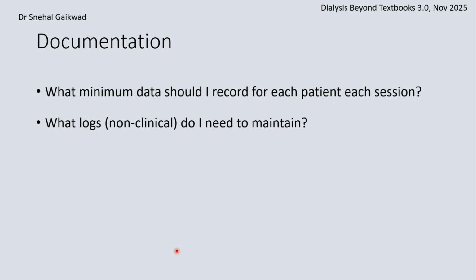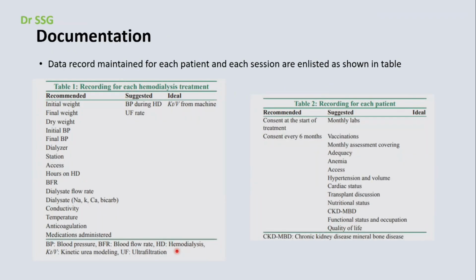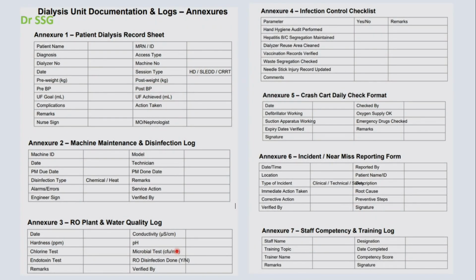So coming to the documentation, what minimum data should I record for each session, and what non-clinical logs do I maintain? The minimum data for each patient per session would be, first, his dry weight and incoming weight, and then at the completion the outgoing weight. Also the vitals of the patient should be recorded at the inception, then ideally every 15 minutes, but at least half-hourly, and should be documented. The machine parameters to be recorded simultaneously would be the blood flow rate, the venous pressure, the arterial pressure, the TMP pressures, the blood flow rate which keeps on fluctuating, so that should be documented every 30 minutes as well. Also the conductivity and all.